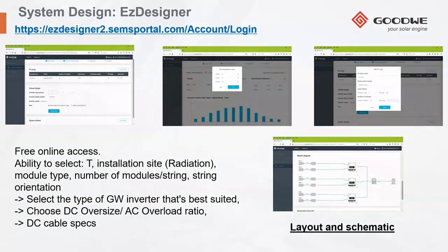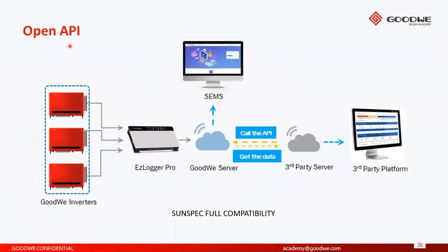The compatibility, the communication protocol of our system is open API. So the communication data are transferred through our data logger to the cloud and can be displayed on the SEMS. But through the exchange of this API, this data can be also transferred to a third-party server, which can be used for, let's say, external elaboration. And also, the communication protocol for our system has full compatibility with the SunSpec, which is the major communication protocol used by the major number of devices in the world.